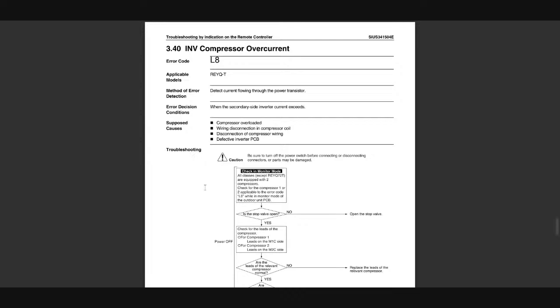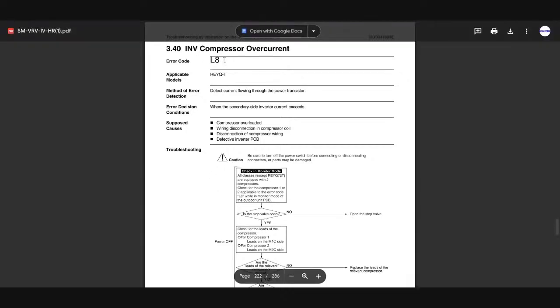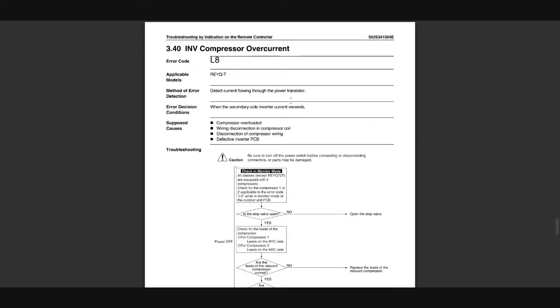Okay, so let's say you go up to a Daikin. This is a VRV 4 series specifically, and you're having an L8 error code. So this would be an inverter compressor overload, and so they give you some basic things. Detected current flowing through the power transistor when secondary side of inverter current exceeded. Decision made, application. So this is the model number.